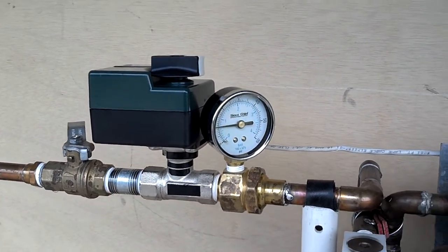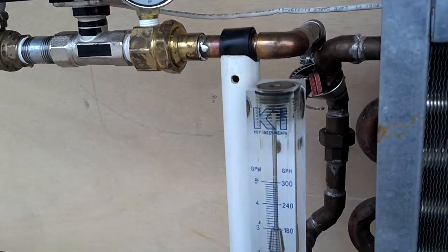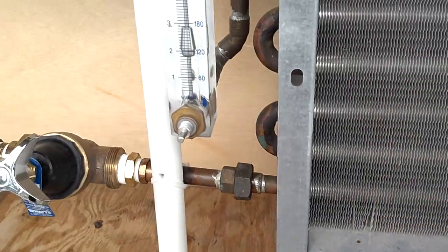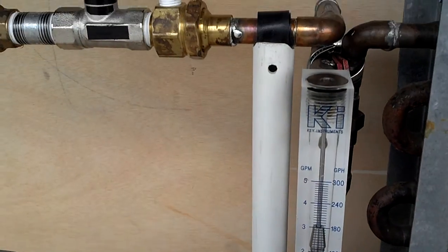It's tied into a manual balancing valve right there. We have 10 pounds pressure and we have it balanced at about 2 GPM. I'm going to close the valve a little bit and we're going to watch what happens with the flow.